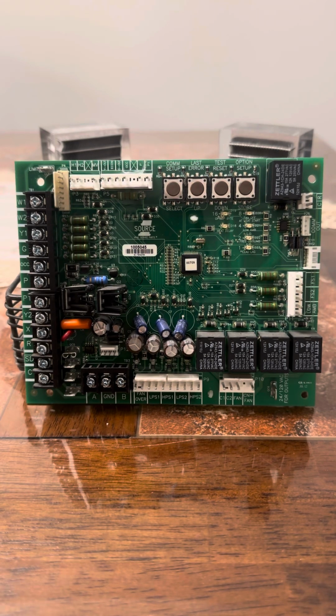So when that happens, if it's turning off too quickly, the heat is dissipating off the heat exchanger, and it's just going to probably trip that auxiliary limit in the blower section or whatever, depending on the model, right? So that could also be an issue in why you're tripping a limit. I have seen those fan delays on these boards not be very accurate. And when that really happens, your best option is to probably just change the board.